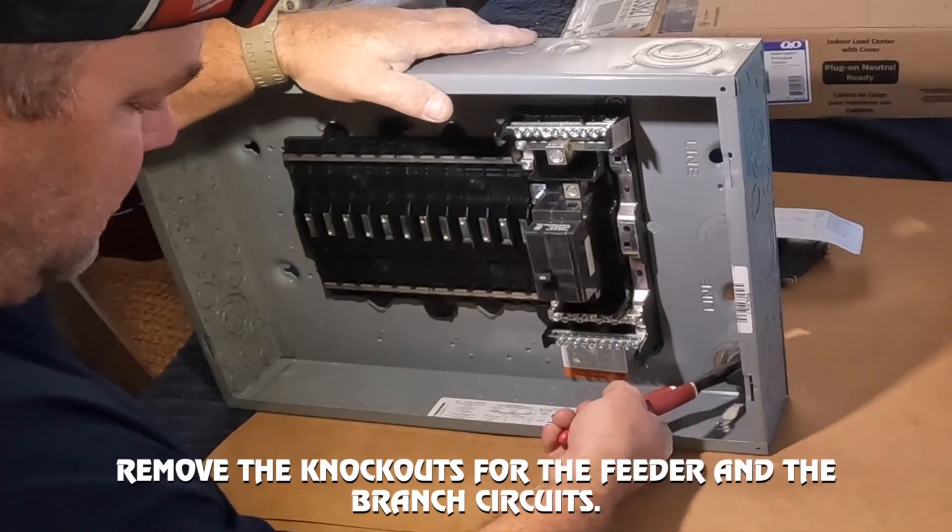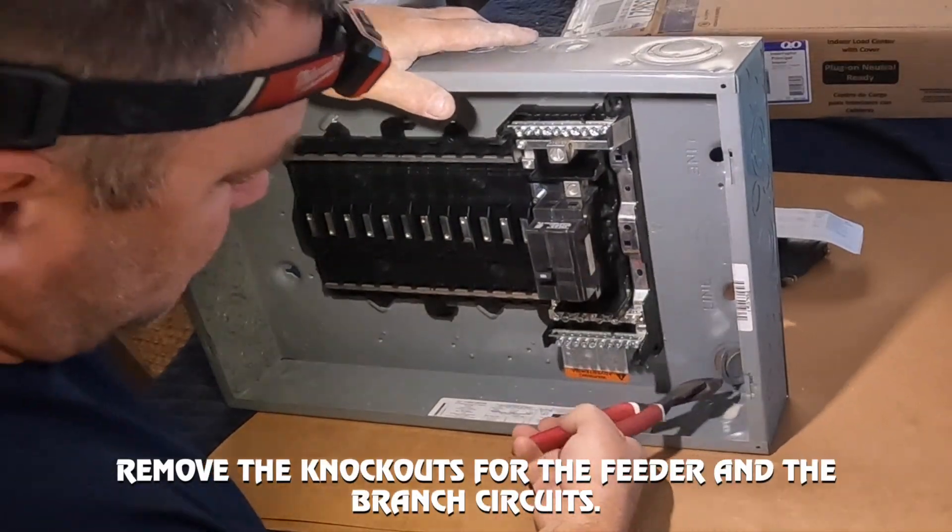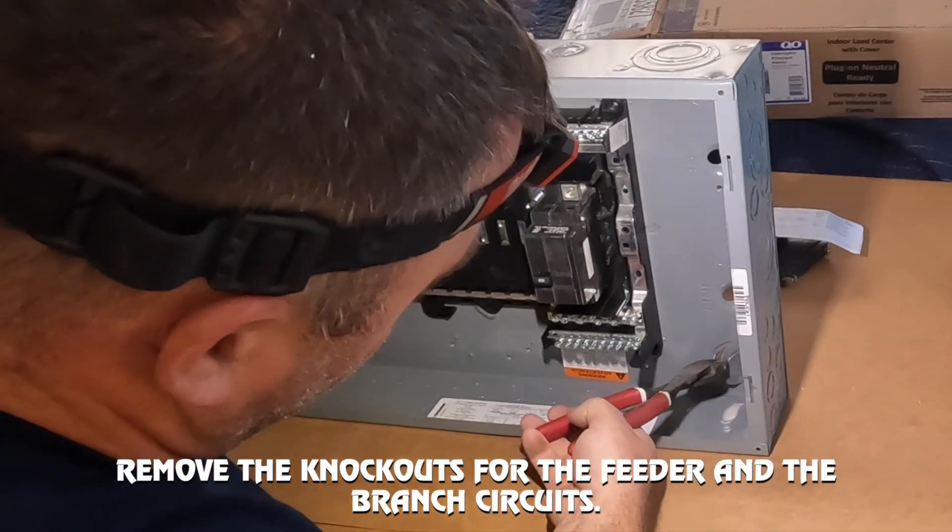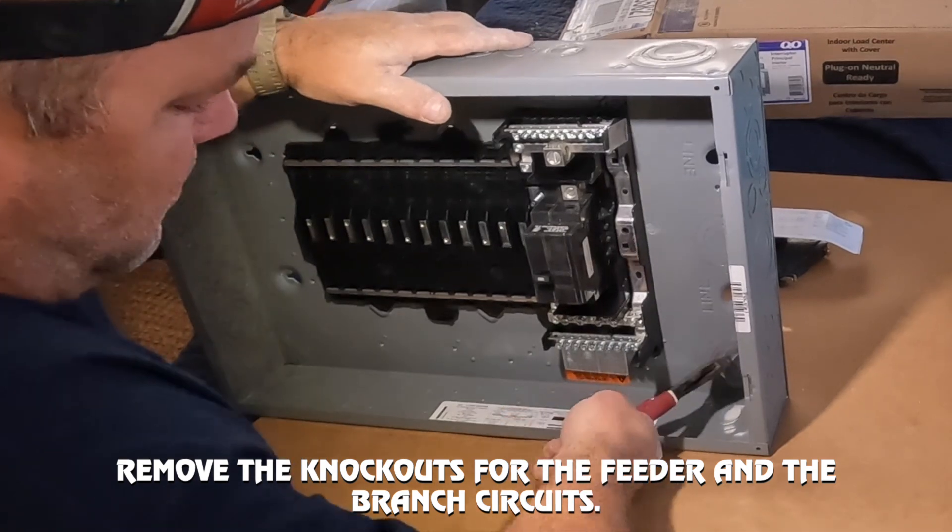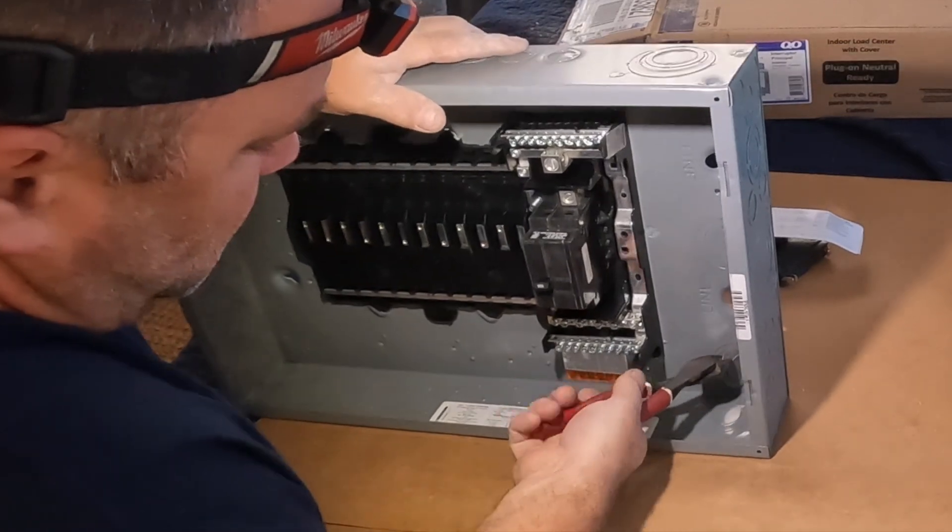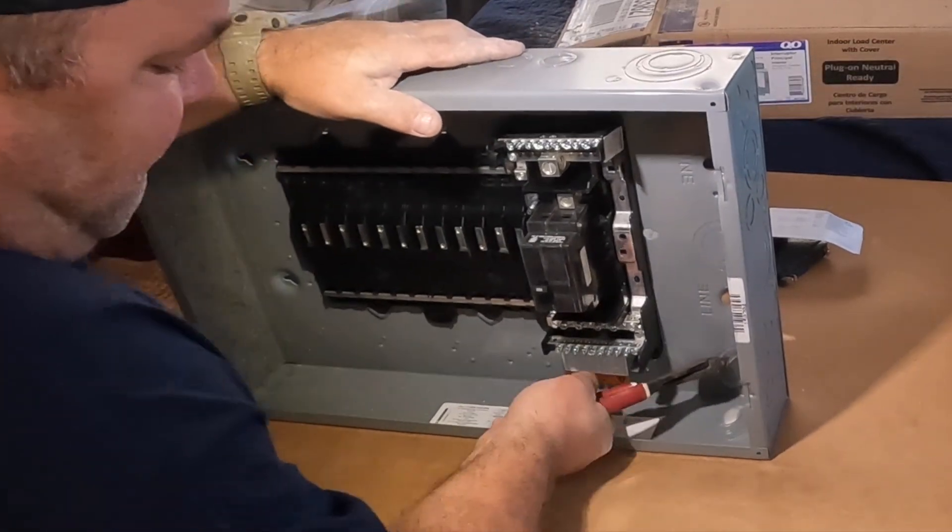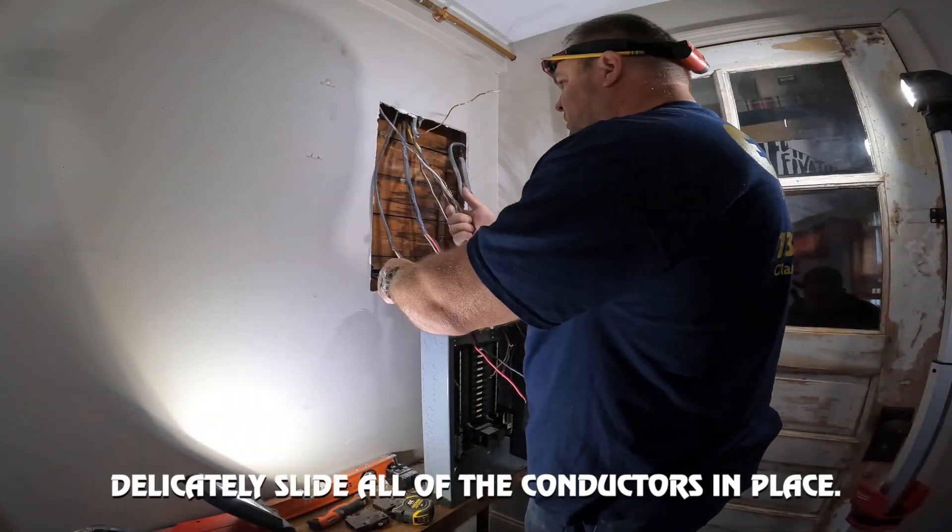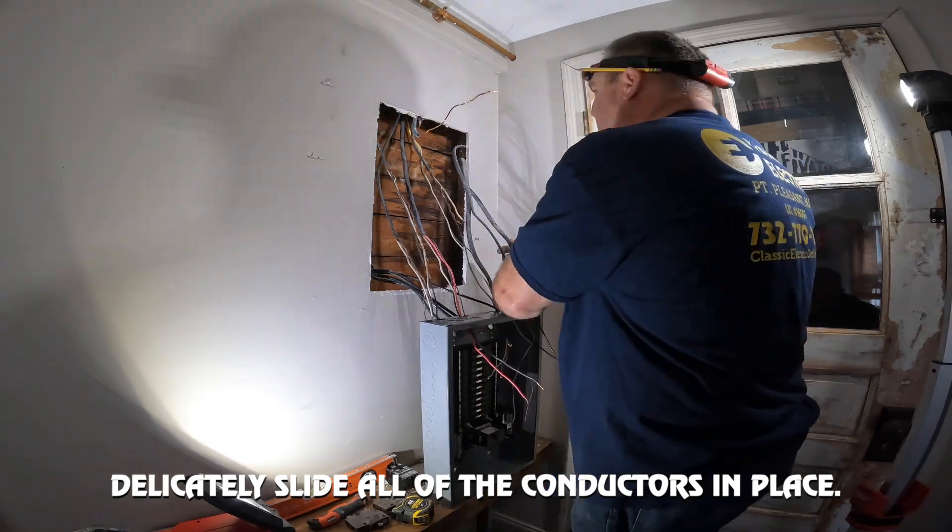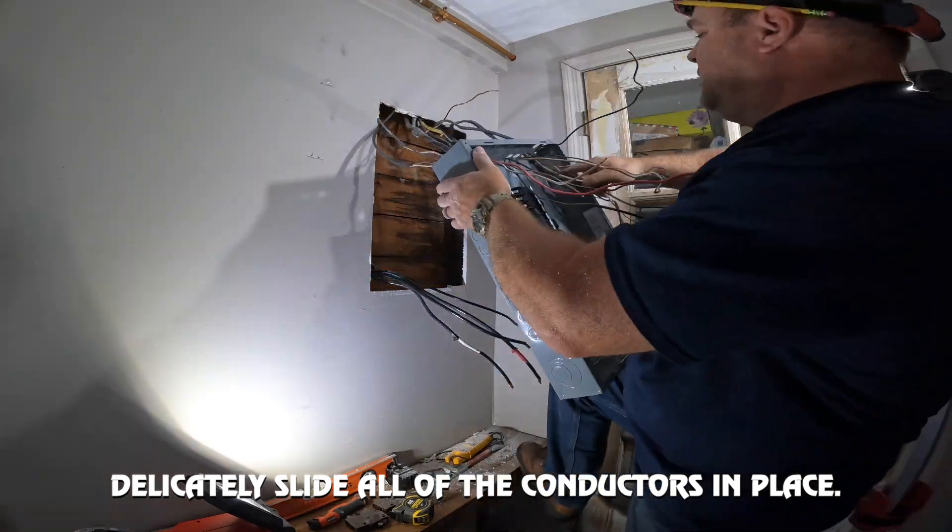What we're doing is we took out that old Federal Pacific panel, which never had the grounds and neutrals isolated. There was a four-wire feeder going to it, but the panel was never updated. So I'm here to update the panel today.